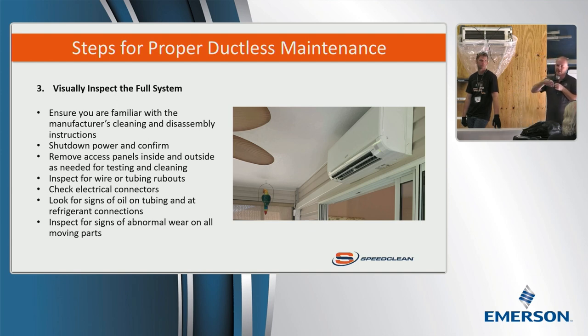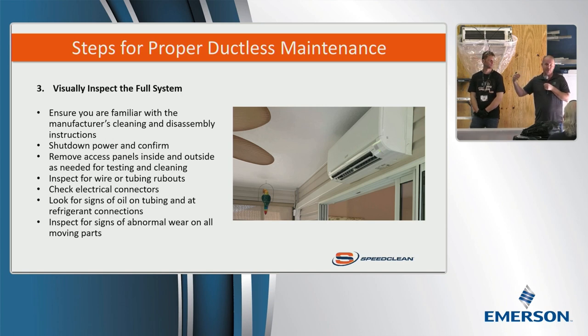Make sure you're not just picking up excess from your ports. But flare leaks are so common, and if you can save a flare leak while you're there—whether on the air handler or the condenser, wherever they are—do it. A lot of times you won't be able to get to them on the air handler, but wherever you see oil, address it when you're there. In terms of value to the customer, that's enormous.